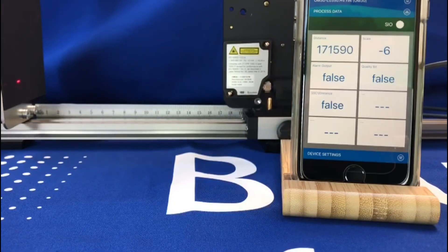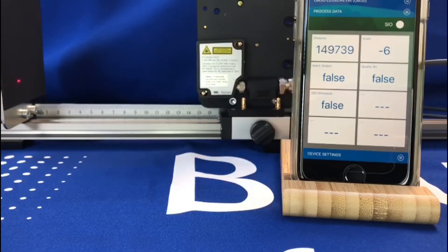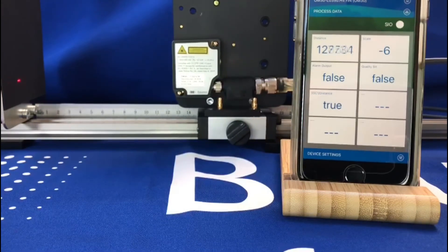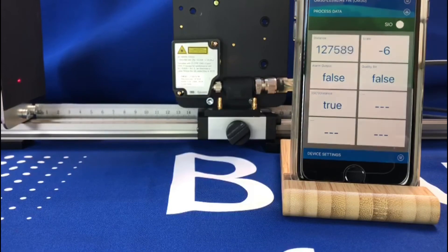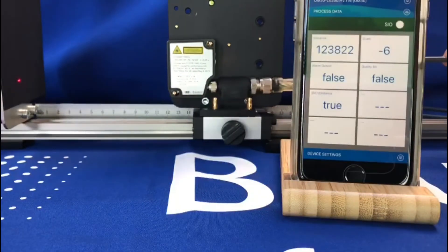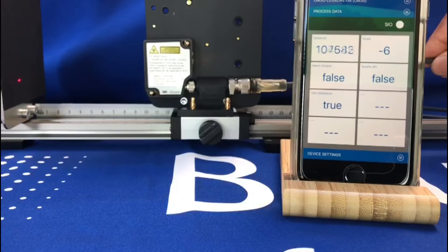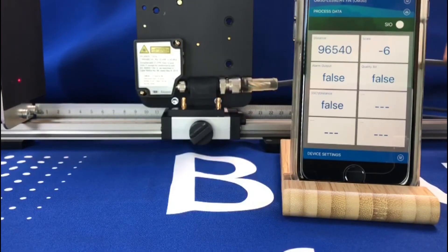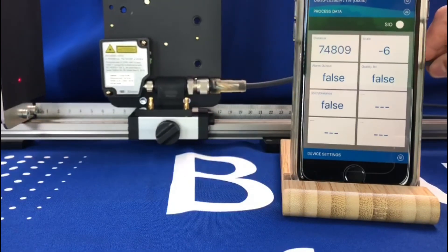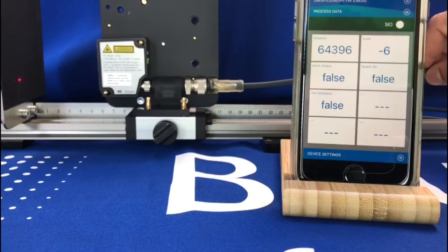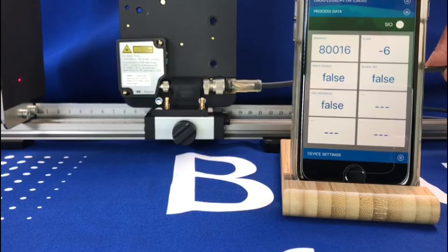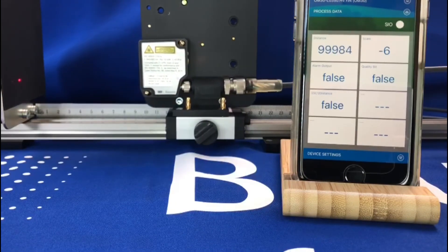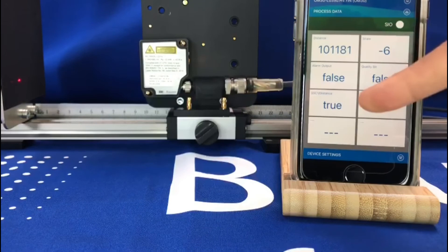So again, 130 mil. As we get to 130 mil inside, so false, it goes to true. So the output is on between 130 and 100 mil. And now it's false all the way up until the dead zone. So again, further and further away, once I reach 100 mil over, the output switches.